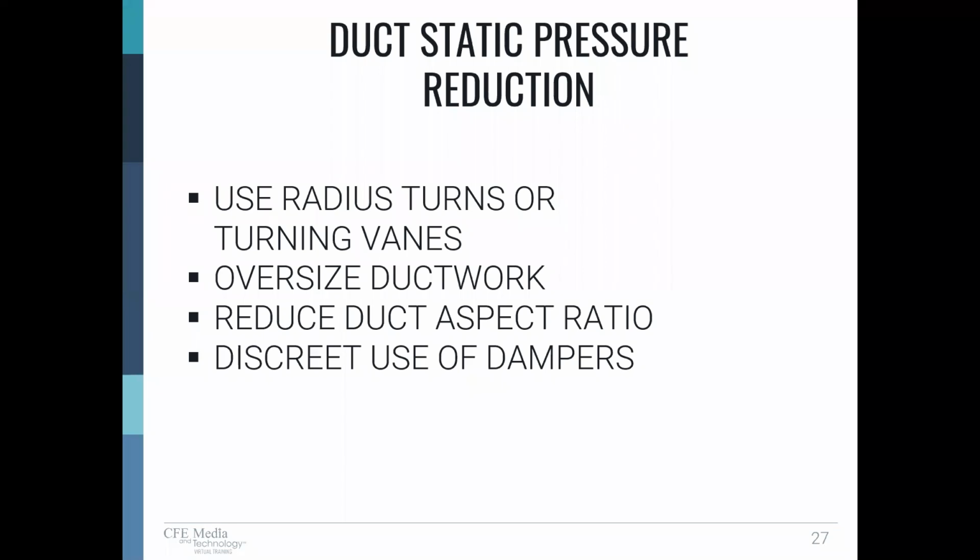And then the last item is the discreet use of dampers. We're going to look at some dampers, and you're going to find that dampers have incredible losses in a duct system. So you need to be very, very careful how you apply dampers.